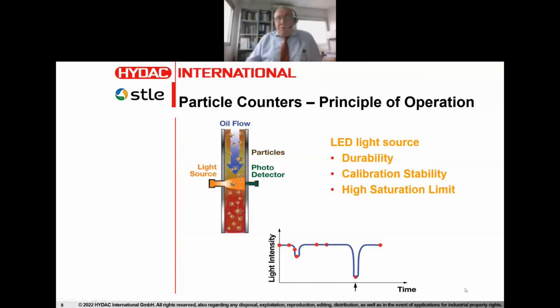A few words, not too much, because I think everybody is well aware of how this works. It's a light obscuration method. You can use different light sources. It could be white light, it could be laser, it could be a light emitting diode. This light is then expanded to cover a certain cylindrical area of the oil flow, and there is a photodetector on the other side, and the decrease in the light intensity detected by the photodetector is then calculated and translated into particle size and the number of these particles.